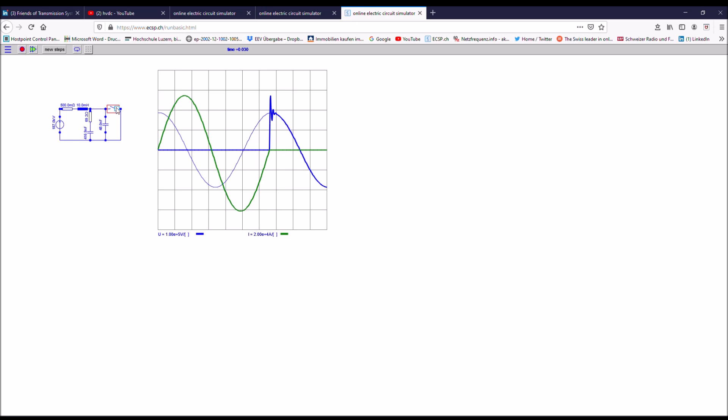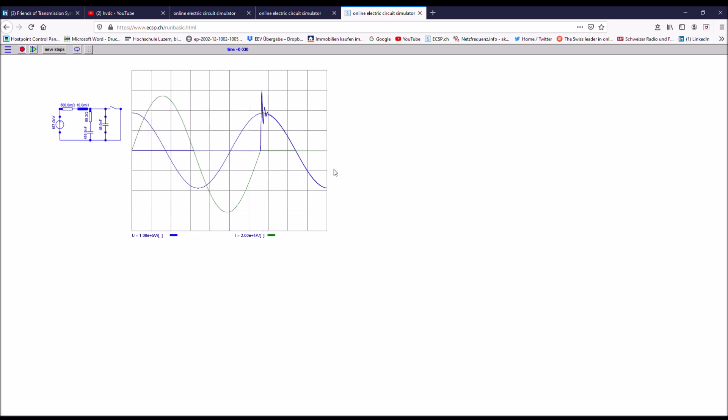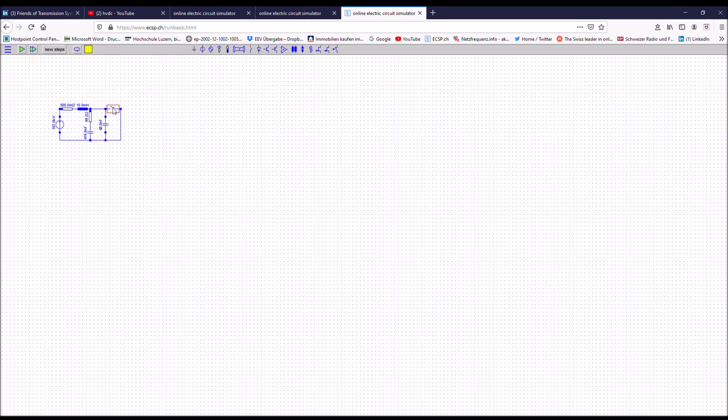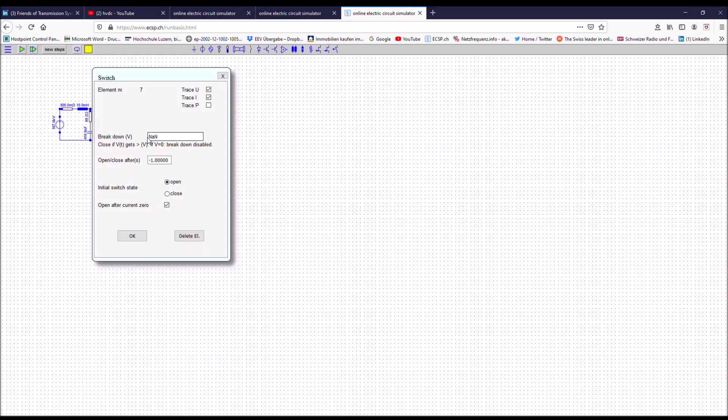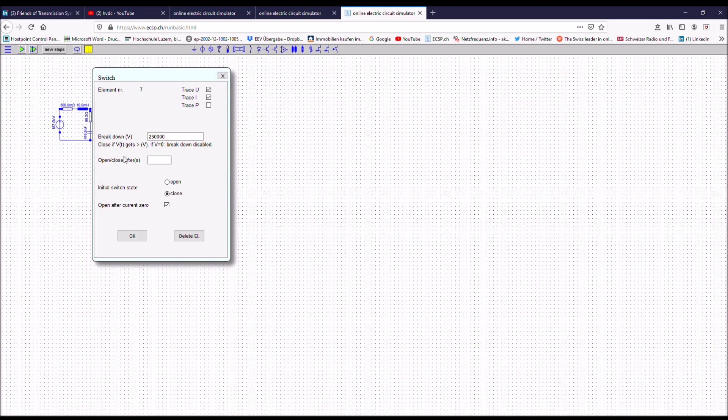Let's change the settings of the breaker again. We would go to a restrike level of let's say 250 kilovolts. This is somewhere in this TRV. And again, I would close the breaker and let it open the contacts after 15 milliseconds. Let's see what happens now.